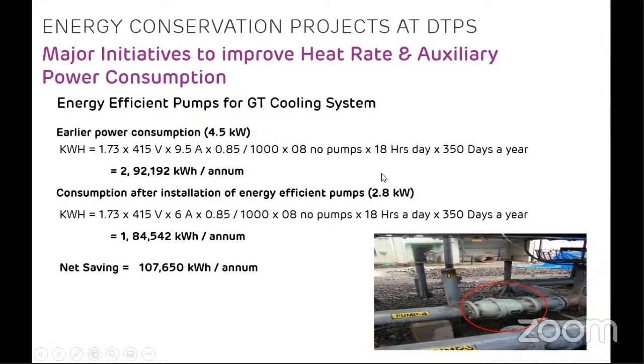There are 8 such pumps which run for 18 hours a day. They run based on the temperature of the transformer. They pick up and drop. So only 18 hours we can consider they run. And for 350 days I have considered, because 5 or 6 days the plant may be under outage.